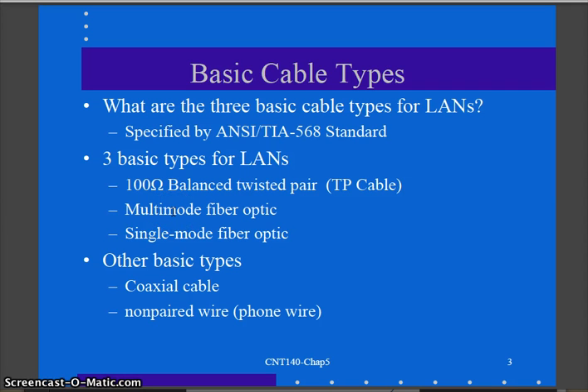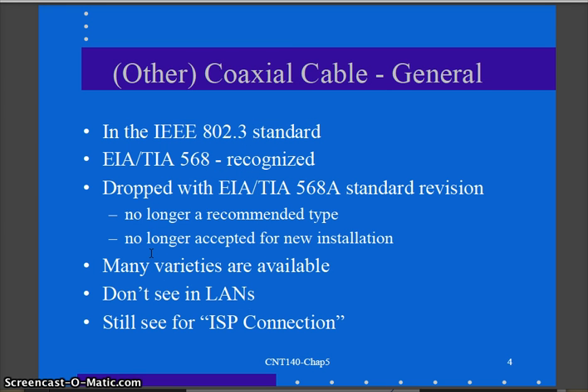We want to take a few minutes on coax and non-paired or phone wire just to touch on them. Coax is grouped into the 'other' category. Once upon a time it was in the IEEE 802.3 standard for Ethernet and was originally recognized by EIA/TIA 568, but as the 568 standard evolved, it got dropped. It's no longer a recommended type of cable and is no longer accepted for new installations.